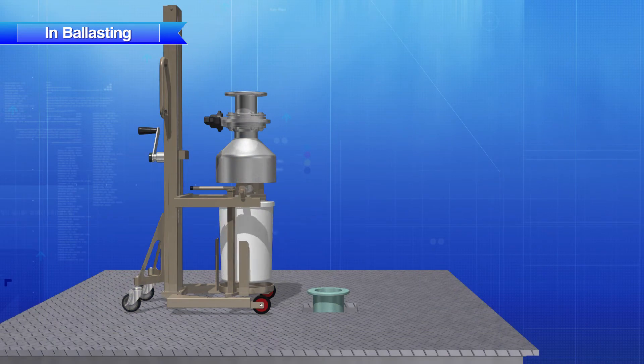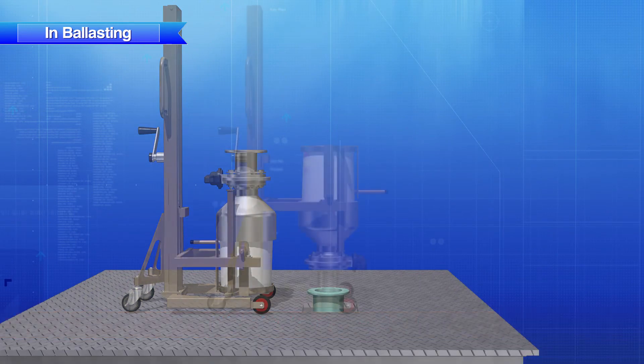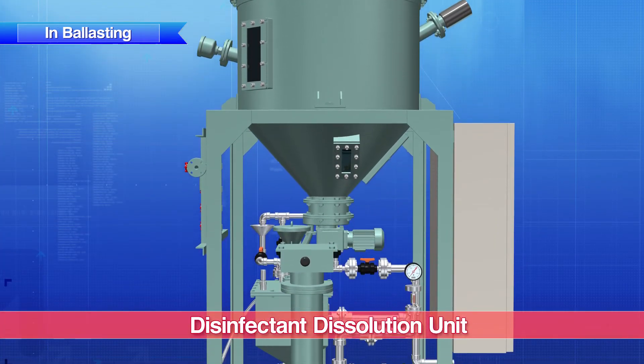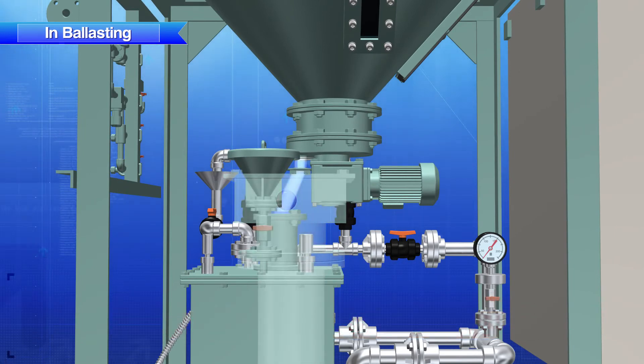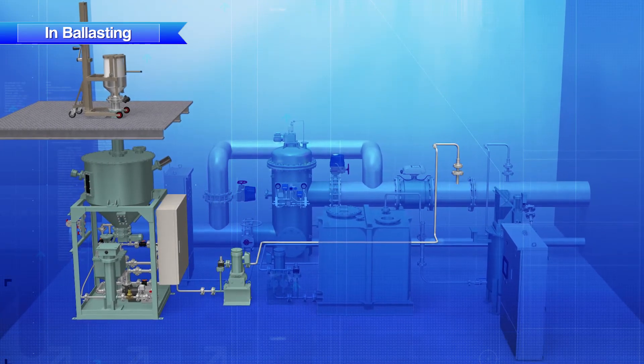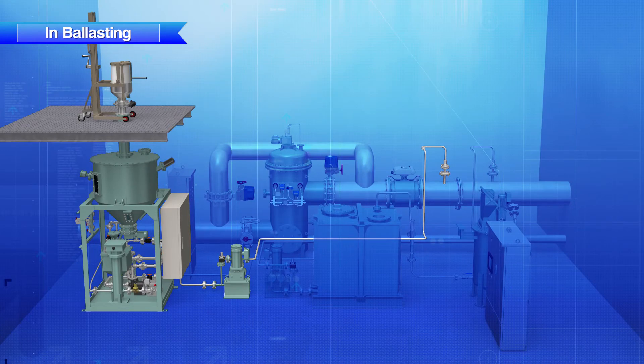Regarding the granular disinfectant: first, a container of the granular disinfectant stored on board is loaded into the disinfectant supply unit. Next, the disinfectant is fed into the hopper of the disinfectant dissolution unit. Once the ballasting operation starts, the appropriate volume of disinfectant is automatically supplied from the hopper to be dissolved. After that, the dissolved disinfectant is injected into the ballast water line by the chemical injection pump.